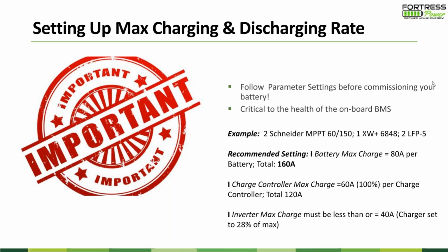After installation, the system working doesn't mean you can walk away. Check your parameters, make sure they're working, then walk away. If you don't check it, there's a good chance a few hours later the customer calls you saying something's wrong. So look at the parameter setting—if it's correct, it usually works fine. If it's not correct, after certain cycles the BMS is going to interact with the inverter and stop giving power or stop taking power from the inverter. So parameter setting is very, very important.